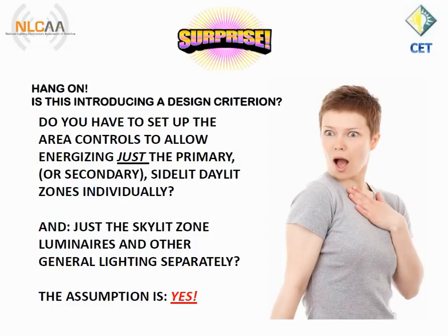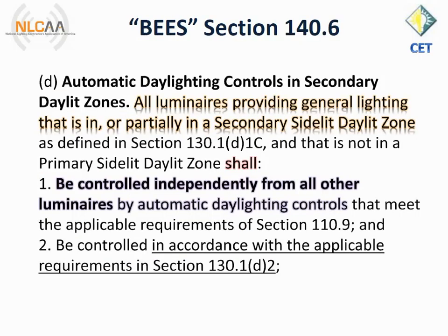From the non-residential compliance manual, and this is not the law, we have the following. 13.8.1 NA 7.6.1 Automatic Daylighting Control Acceptance, Functional Performance Testing, Step 2 No Daylight Test. Quote, when conducting this test, the other lights in the space should be turned off. Simulate or provide conditions without daylight. That is out of the 2013 version of the non-residential compliance manual. And like I say, that is not the law. The manual is just meant to be helpful advice.